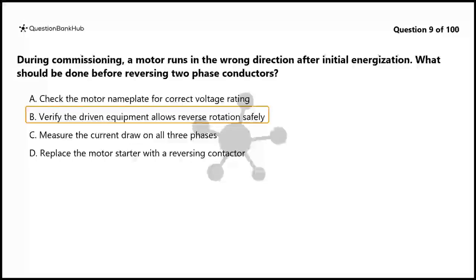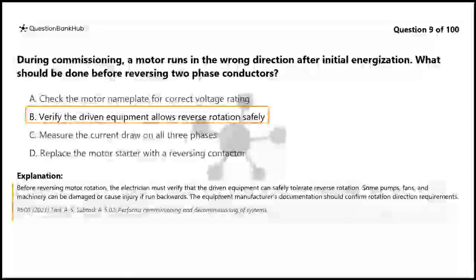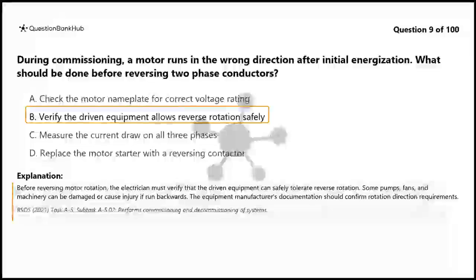The correct answer is B. Verify the driven equipment allows reverse rotation safely. Before reversing motor rotation, the electrician must verify that the driven equipment can safely tolerate reverse rotation. Some pumps, fans, and machinery can be damaged or cause injury if run backwards. The equipment manufacturer's documentation should confirm rotation direction requirements.